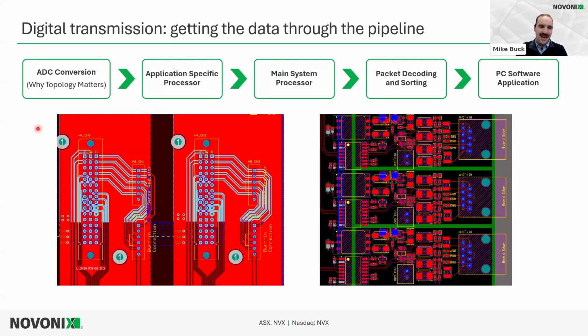The processor then has an operating system on it and different controls, and that's sent through a packet through Ethernet. And then the packet is sorted and parsed into the application that you see on the PC. And that's where there's the database, and the data entry is collected and then processed for the customers to view. And so we can't negate the digital side, because if we can't process the digital bit stream through accurately, then we can't collect the data the way we want, and the measurement precision and accuracy was all for null.